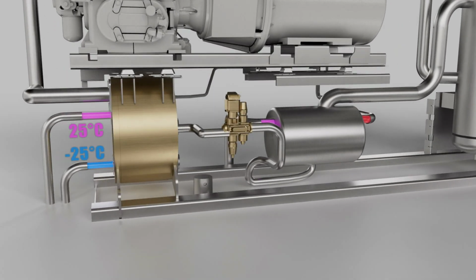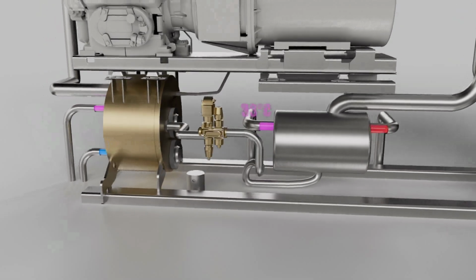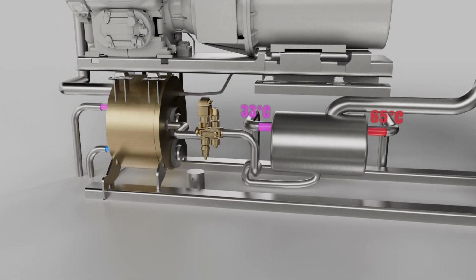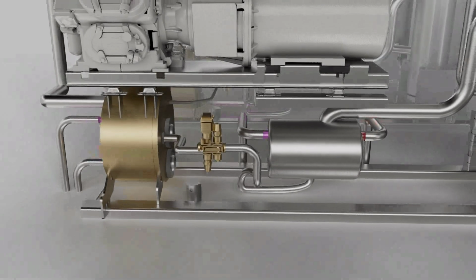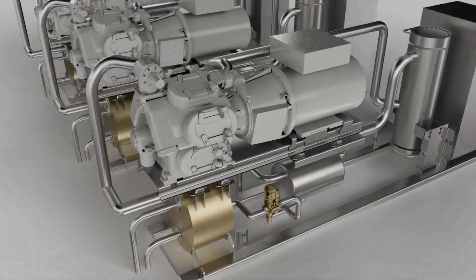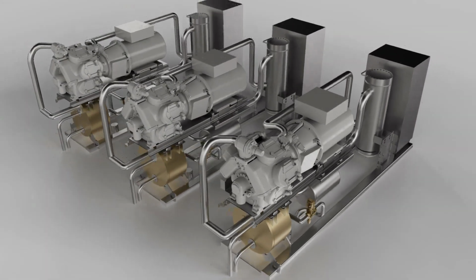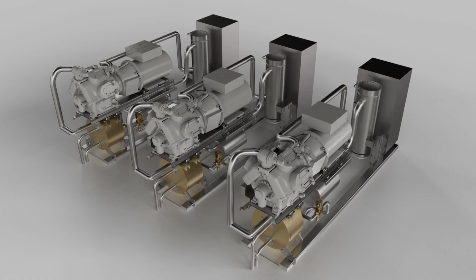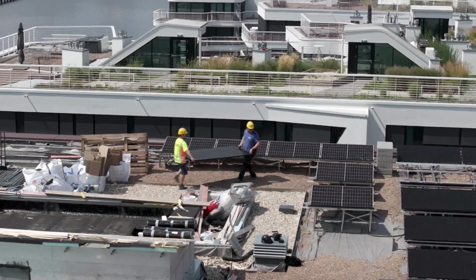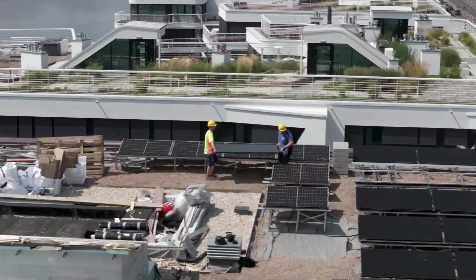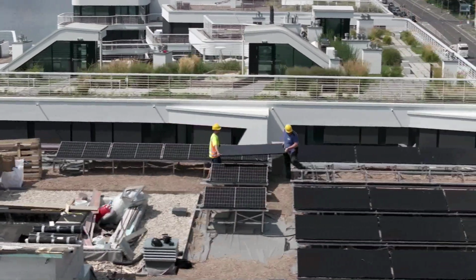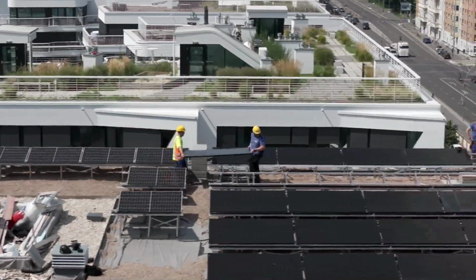This cools the brine circuit on one side and heats the water circuit on the other, which means that thermal energy is raised to a higher level. Due to the high energy density of the ammonia and the special design, the heat pumps operate with a high thermal output and are very efficient overall. The heat pumps are working all through the winter. The water in the storage tank freezes through before the end of the heating period.